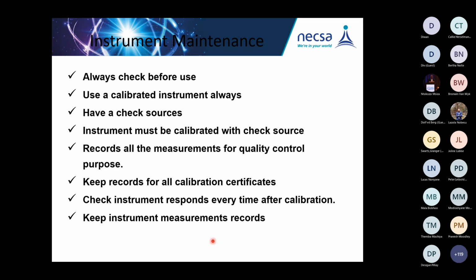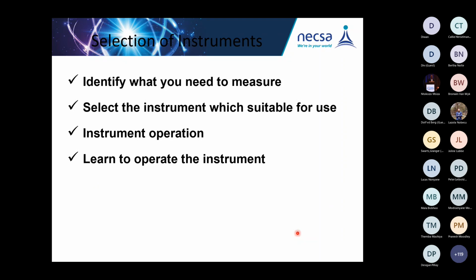Keep records of all the calibration certificates. The calibration certificate will assist you to check the response and the behavior of your instrument by looking at the calibration factors, and also the percentage deviation or the uncertainty as reported in the certificate. And keep all the instrument measurement records, because when the instrument starts reading abnormally, you can pick it up since you have a good, strong record.